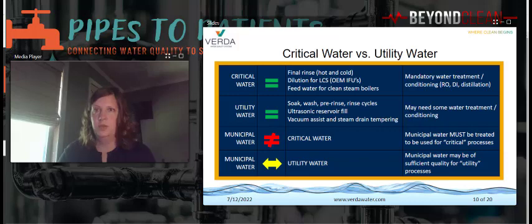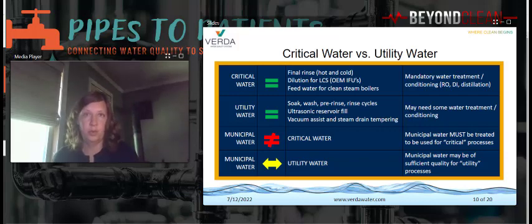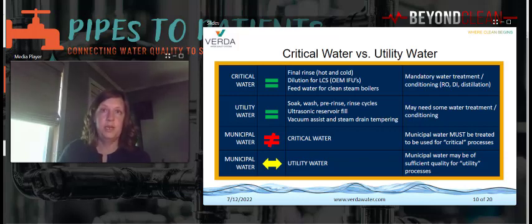So, critical water versus utility water. Let's define what they are and aren't, and why utility water is important and often neglected. When most healthcare facilities think about water quality for sterile reprocessing, they're thinking about critical water. So what is critical water? Primarily, it's water used for the final rinsing of instruments. This could be during manual washing, ultrasonic cleaning, or in the final phase of an automatic washer disinfector. It's also used for dilution for liquid chemical sterilization equipment, depending on the OEM's instructions for use, the IFUs. And it can also be used for feed water for clean steam sterilizers, but more on that later.